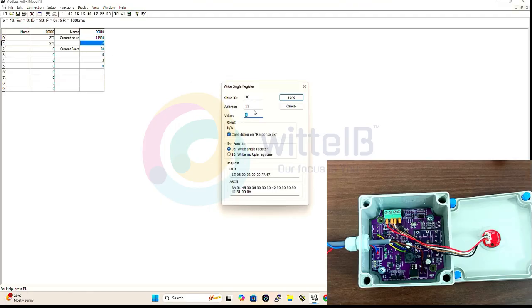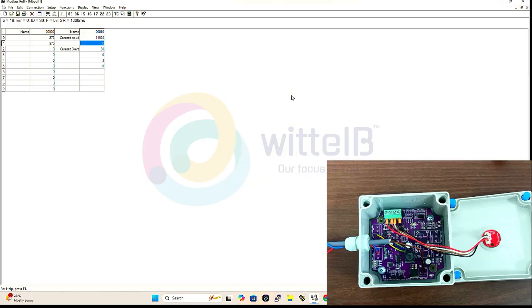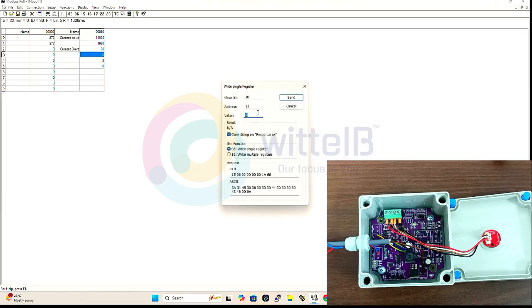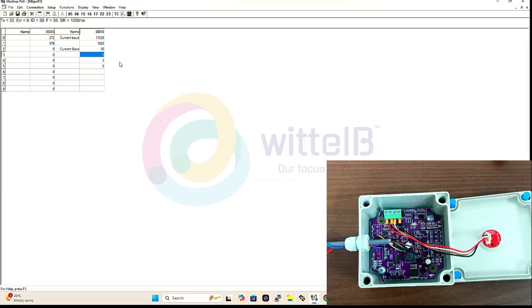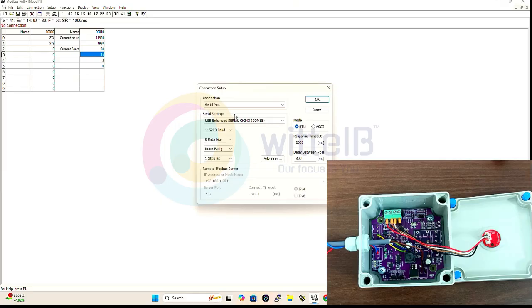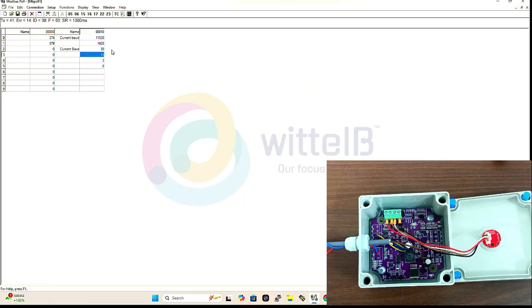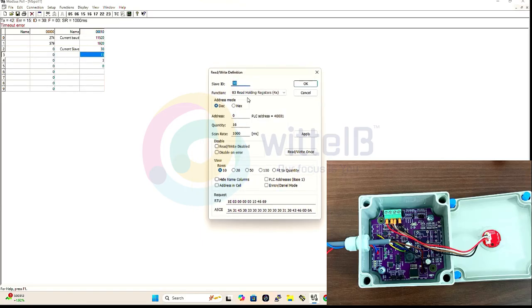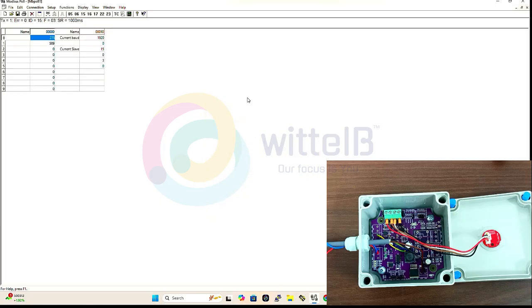Now I will provide 19200. For that I will provide 1920. Send the request, and I will set the slave ID as 15. Send the request. See, the user set 1920 and the slave ID as 15. Now I will press the reset. See, here I get the timeout error. Now disconnect the board and connect the board with the new settings. Here I will go for 19200. Click on that. Then go to setup and change the slave ID to the new one, that is 15. Then enter. Here the board is communicating with the new slave ID and baud rate.